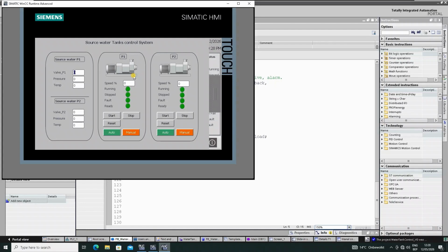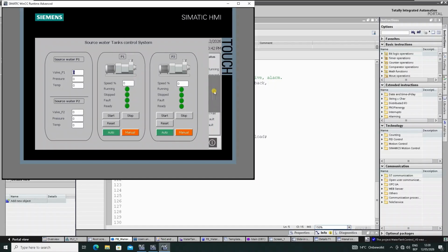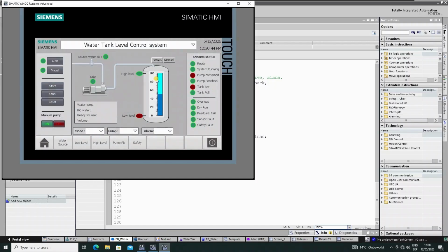So that's why you have to use, for example, a logic. If it's turning dry, you have to have a sensor somewhere. If the sensor doesn't sense water in 2-3 seconds, it should shut down the pump automatically, right?